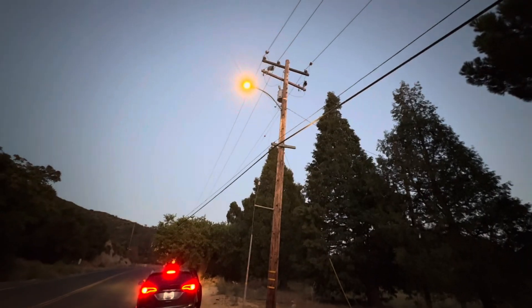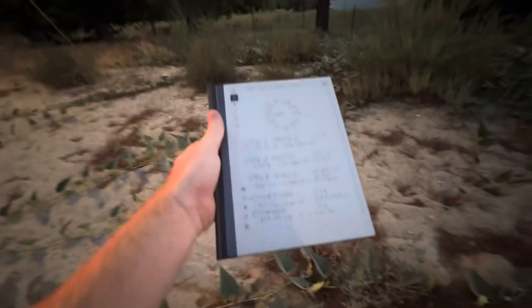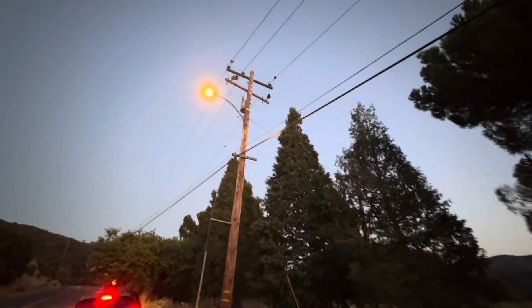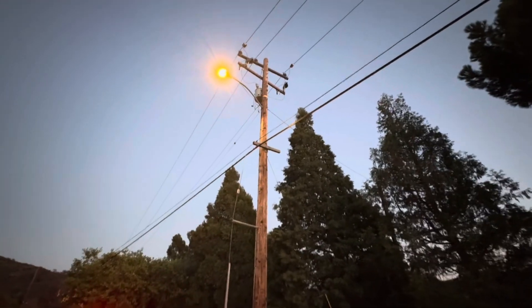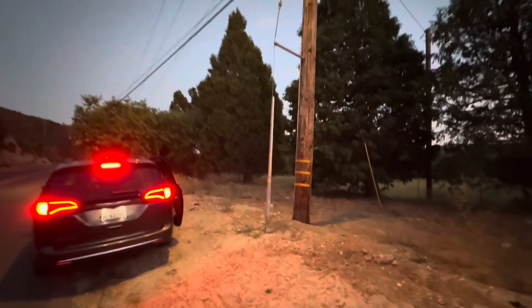We've got another one here on Pine Canyon Road, just east of the mailboxes. This is number 5 on my list, at 18518 Pine Canyon Road. There's a mailbox and an entrance to the house, and the pole is just east. It's the south side — the side opposite the streetlight — that's arcing.